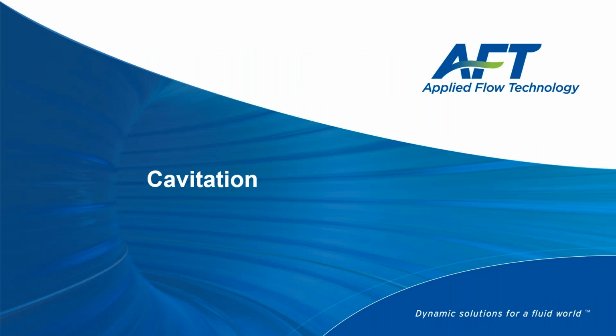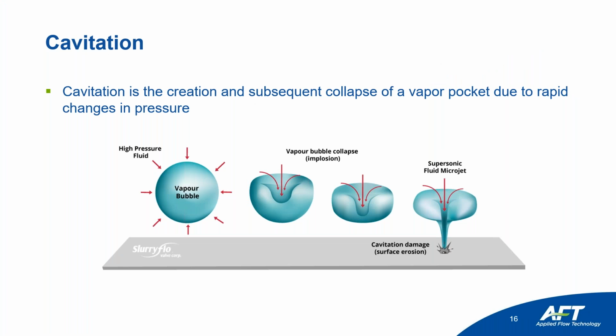Okay, second topic that I wanted to talk about today, kind of a rough transition, I'm sorry, is cavitation. Don't do that. Cavitation is not good. But before we can really understand why it's not good, we have to understand what it is. Cavitation is the creation and subsequent collapse of a vapor pocket due to rapid changes in pressure.